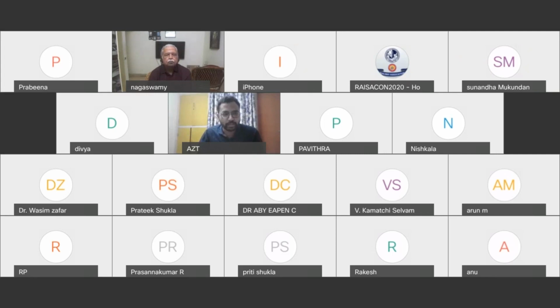MRI compatible anesthesia machines with piped anesthetic gases should be available. All gas cylinders are to be MR compatible. Special monitors that we can use inside with some modifications include pulse oximetry with fiber optic cables. We can use capnography, but there is a delay in obtaining signals as the sampling tube will be longer. And NIBP can be used safely, provided the connections of the cuff with the hose are secure.